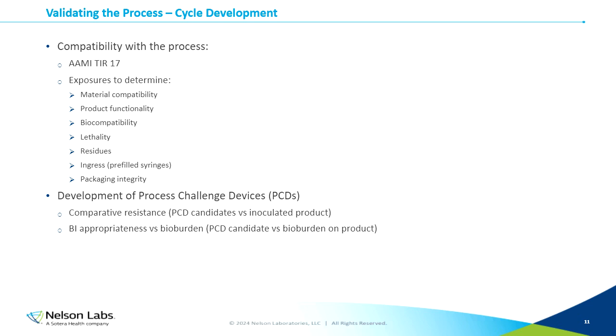That's looking at the resistance of our process challenge device candidates versus the inoculated product, where we put biological indicators inside that product and compare it to our process challenge devices that we may be considering. And then another thing that we can look at when we perform fractional cycles is the BI appropriateness versus the product bioburden. So we may run the process challenge device candidate versus the bioburden on the product. Does the bioburden show less resistance than our PCD candidate? We would expect that to be the case, but that's something that we often will look at just to confirm that it is true.